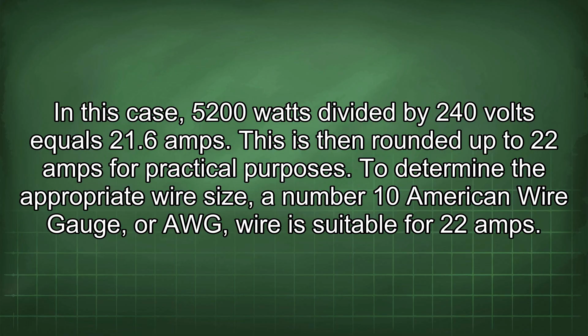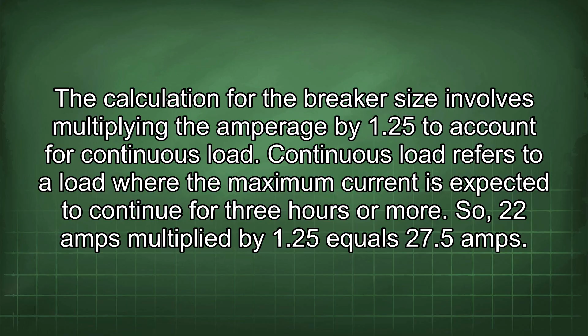The calculation for the breaker size involves multiplying the amperage by 1.25 to account for continuous load. Continuous load refers to a load where the maximum current is expected to continue for 3 hours or more. So, 22 amps multiplied by 1.25 equals 27.5 amps. This is then rounded up to the next standard breaker size, which is 30 amps. Therefore, a 30 amp breaker is appropriate for this circuit.